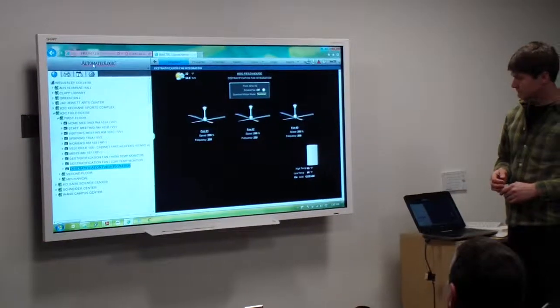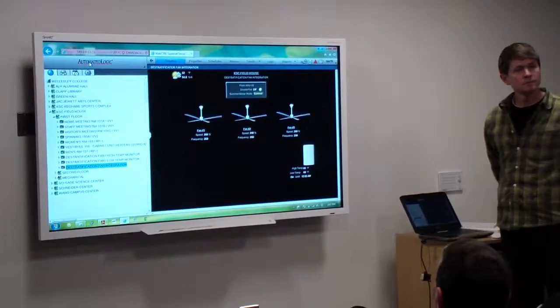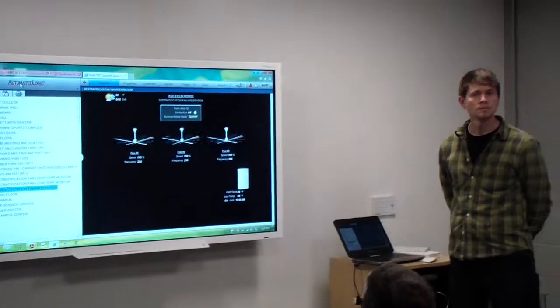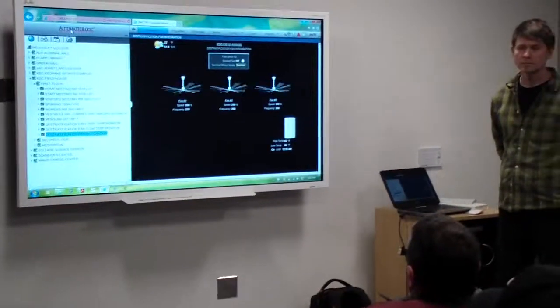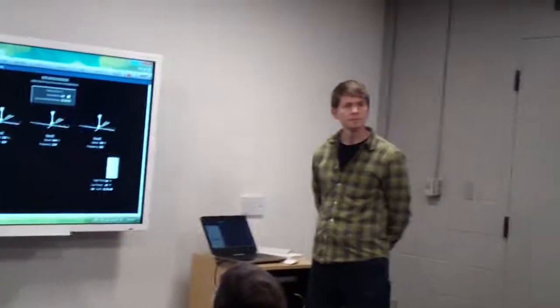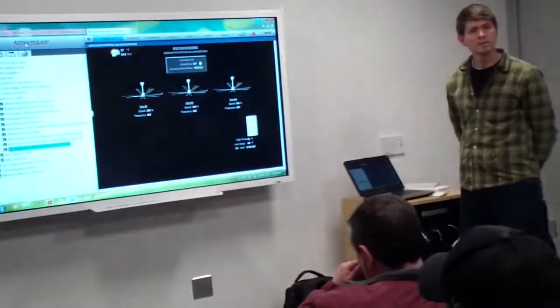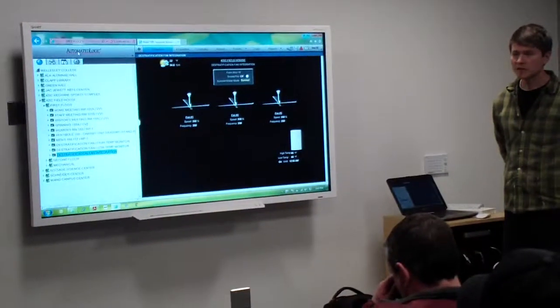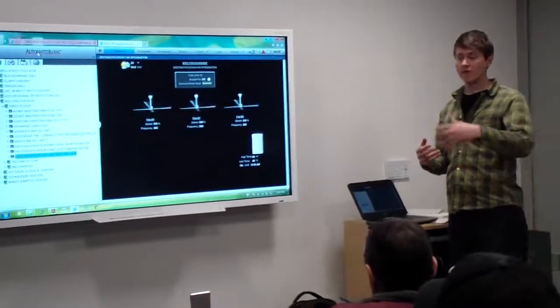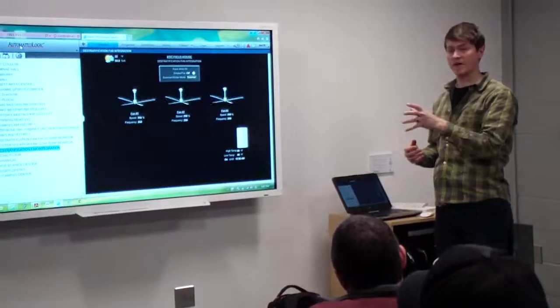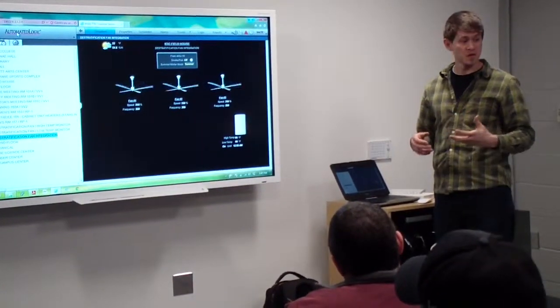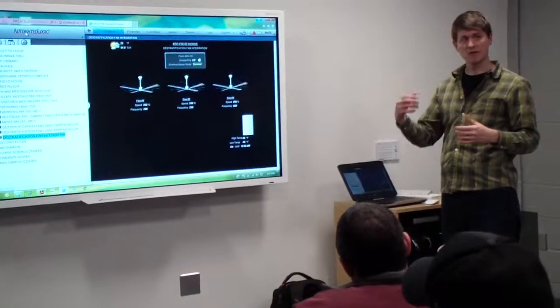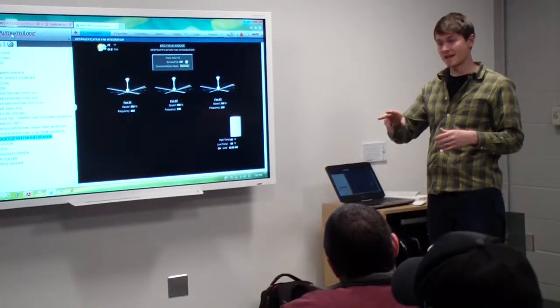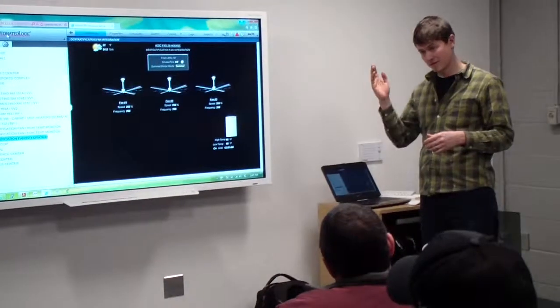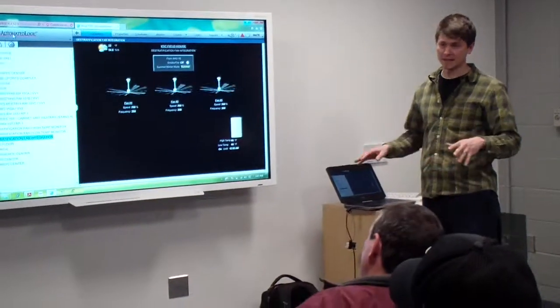As well as fire alarm, they shut off on fire alarm. So there's a shunt that shuts those off, but they're tied into the controller that's down over here in the last storage closet. As soon as you reset the fire alarm, the fans kick back on. I take an input from the fire alarm device, so when the units go into alarm, it sends that input into the card, and then the card removes the run command from the fan, and the fan shuts down.